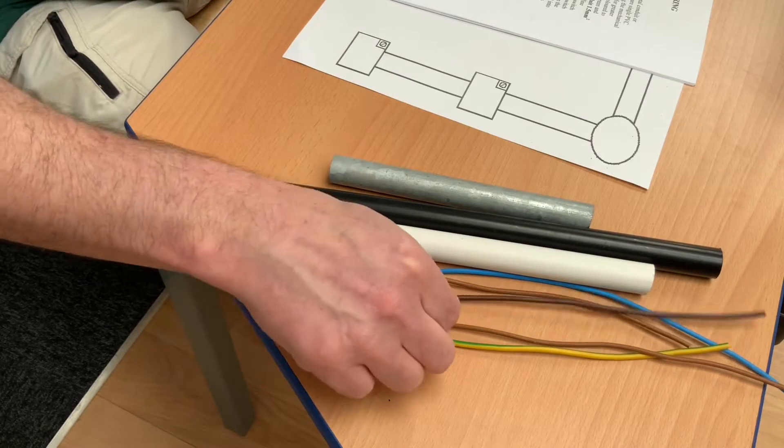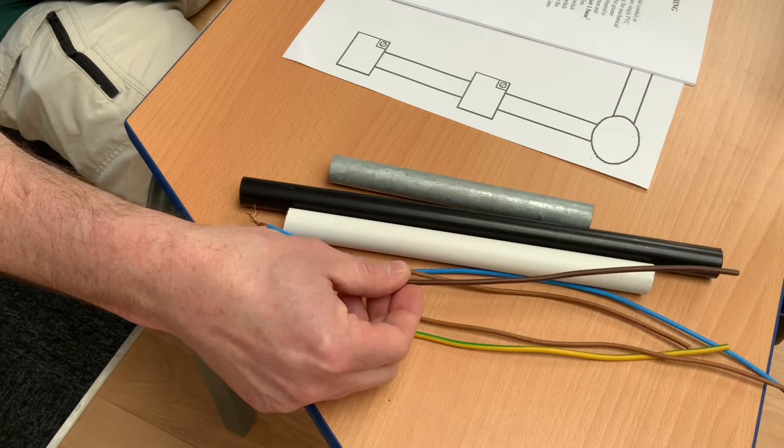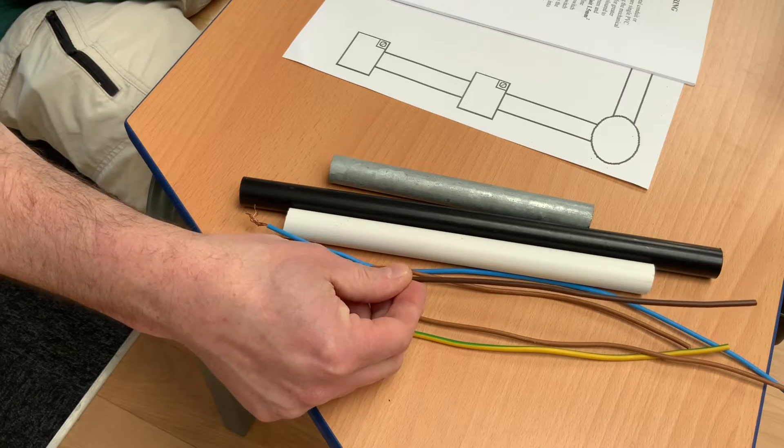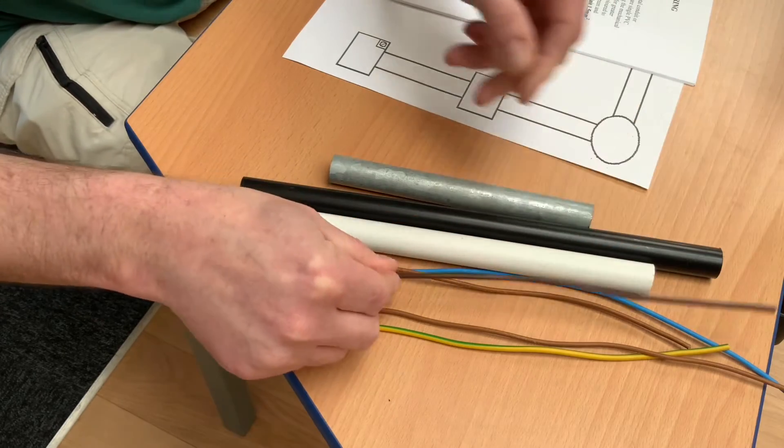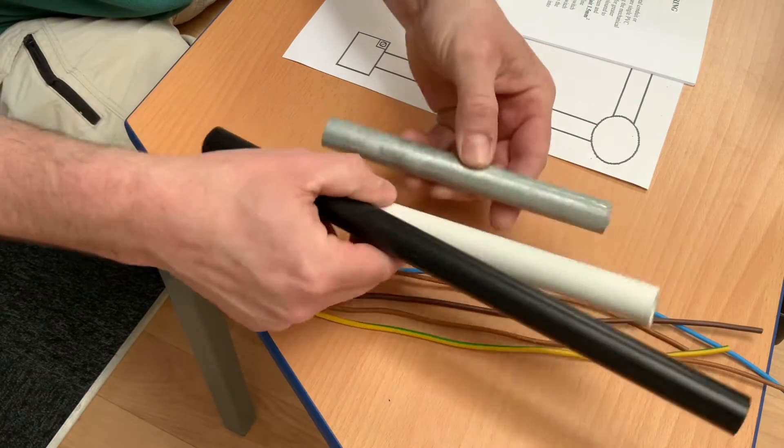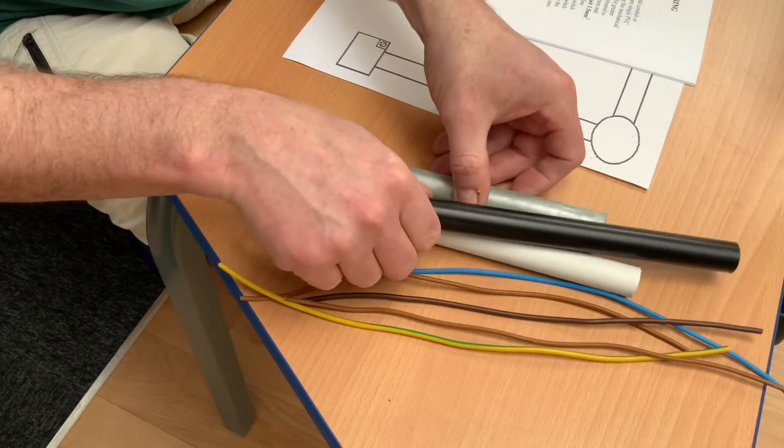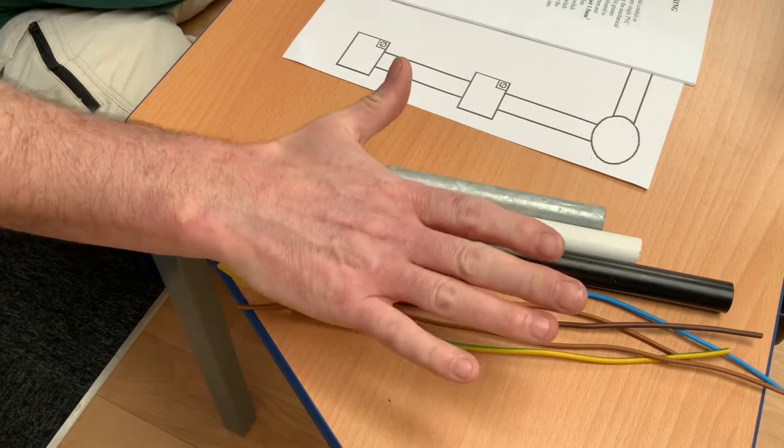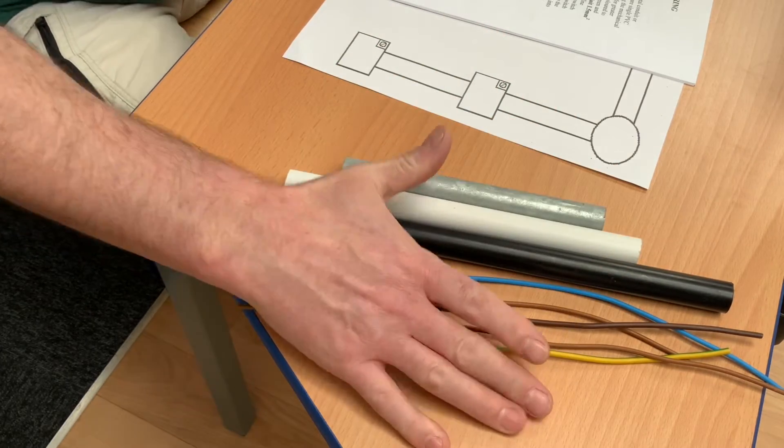We're practicing this different way of wiring lighting circuits using the conduit looping method. Remember we're now using single insulated PVC cables, probably 1.5mm squared, stranded for greater flexibility. These are the cables we use within conduit and trunking systems, with the advantage being we can take the conductors exactly where we need them.